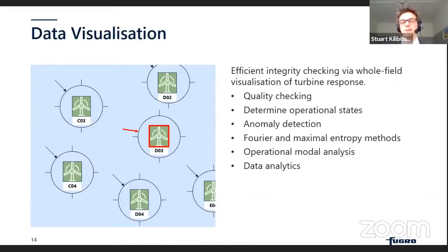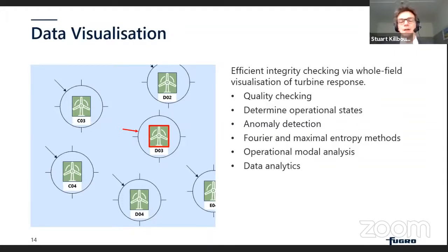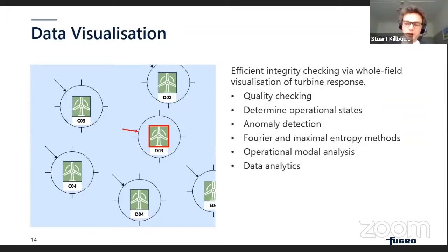Another approach to anomaly detection is to exploit the full array: with instrumentation envisaged on all units — potentially 50 or 100 in the future, though initially three to five for pre-commercial checks — we can compare the response of all different units, perform cohort analysis, and identify any unit not behaving like its neighbors, flagging potential problems for investigation.